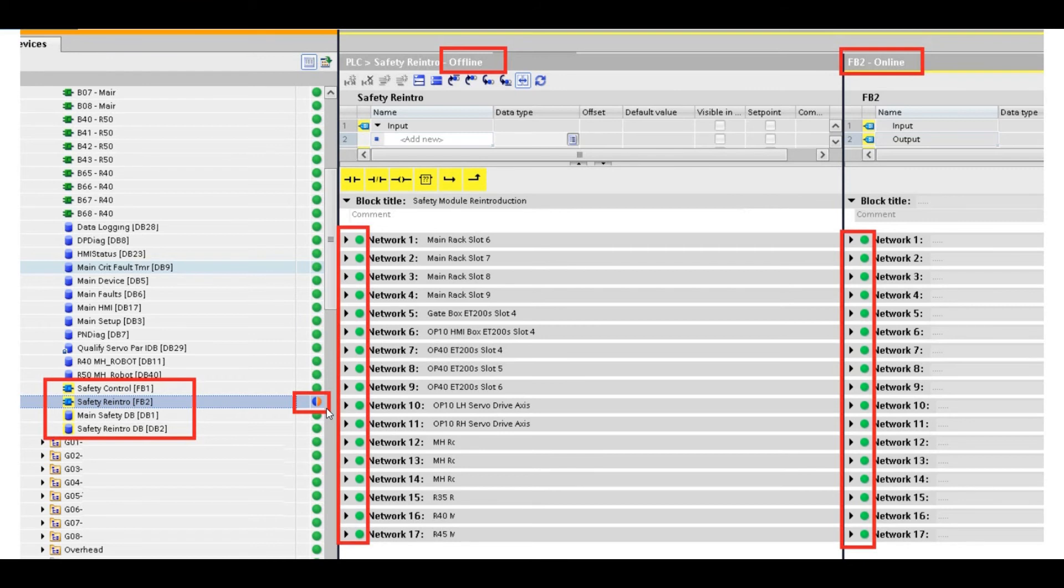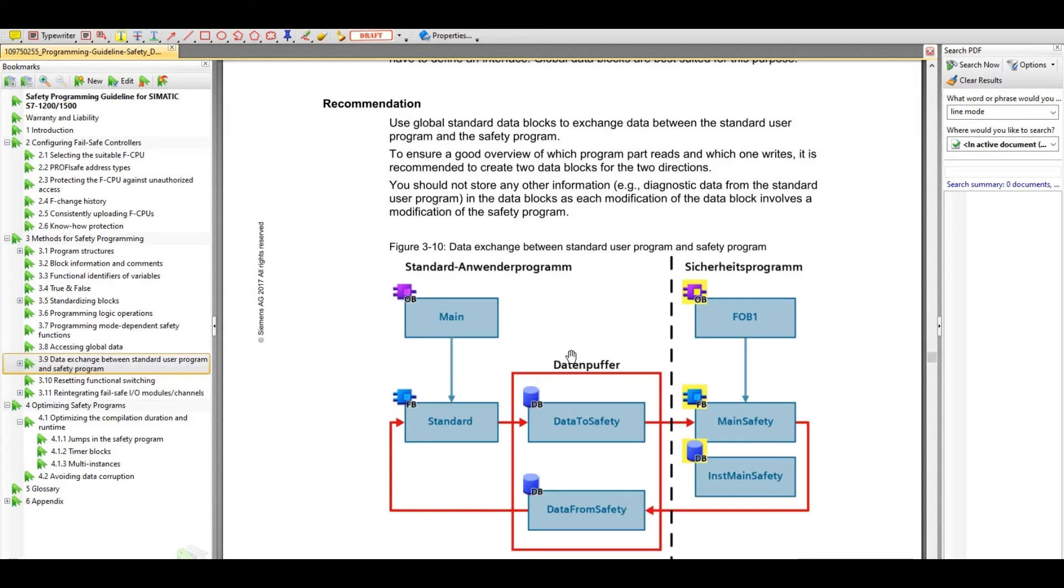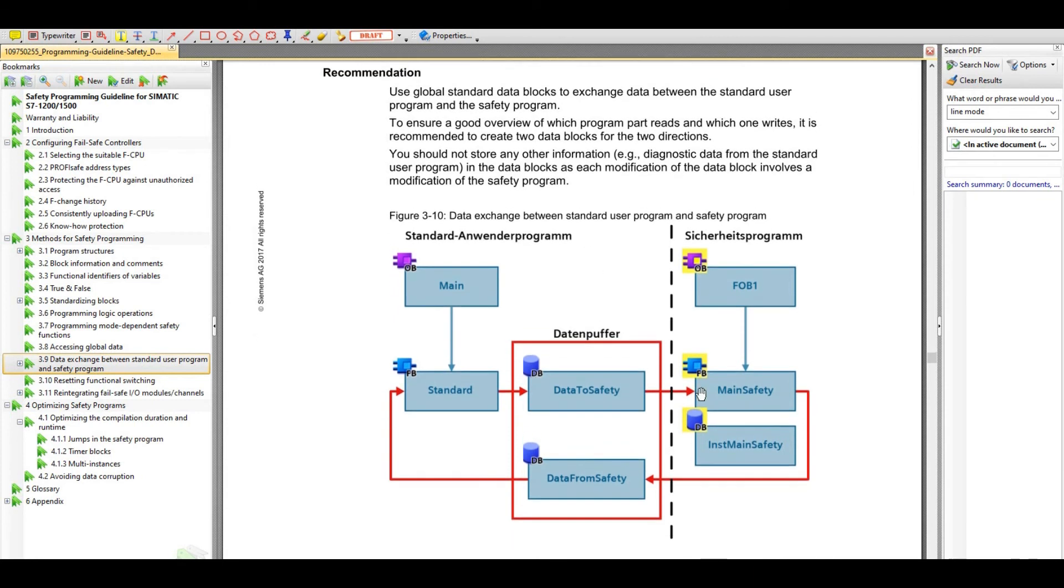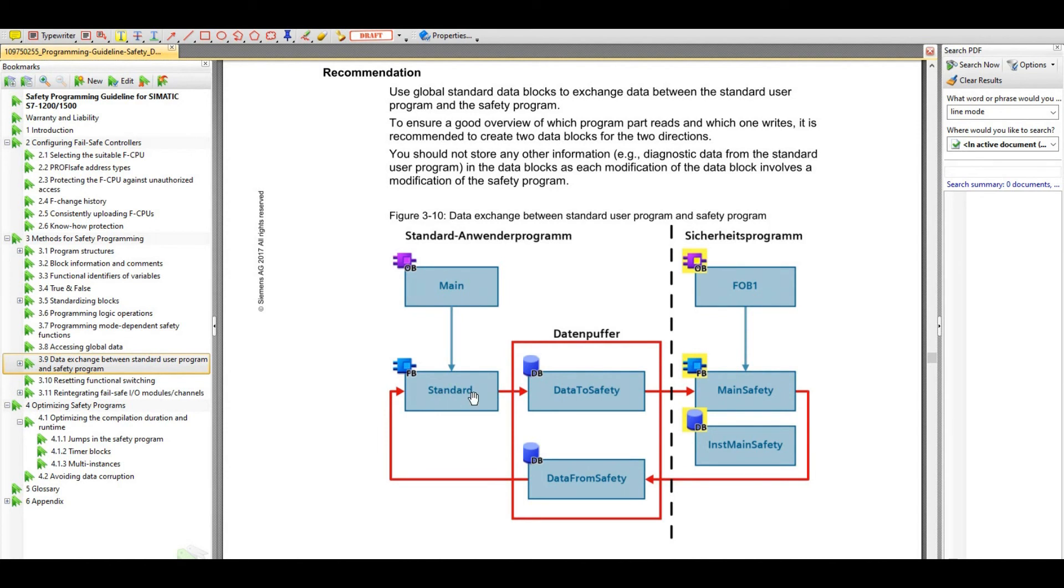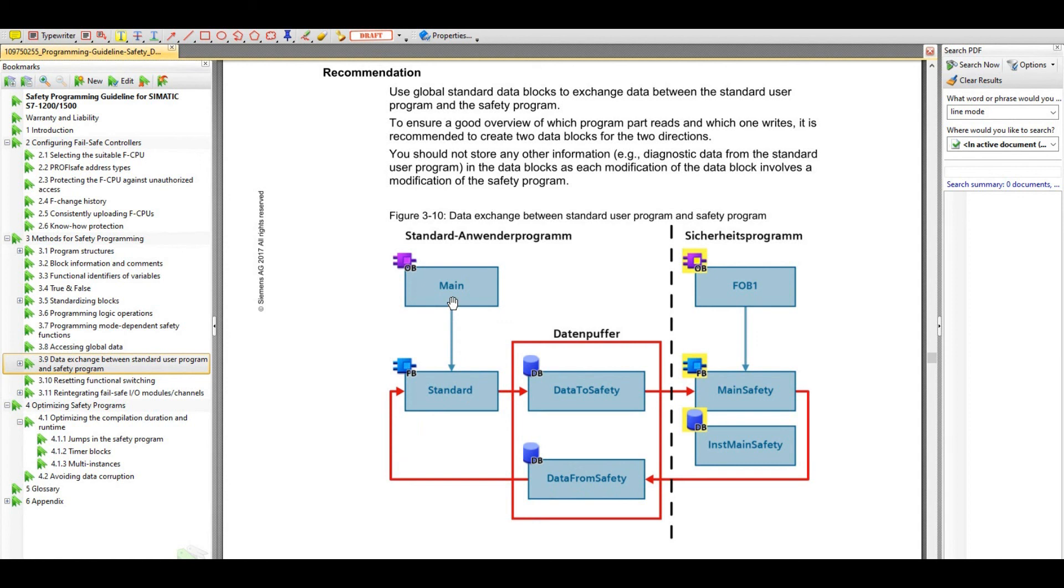The best way is when you design the project, if your project is using a safety controller, Siemens safety controller, you better follow this guideline. It is inevitable to exchange the data between the normal and safety logic. The best way is we create two interface DB. One interface DB plays the role to exchange the data from the standard to safety, and one DB gets the signal from the safety and transfer to standard PLC.